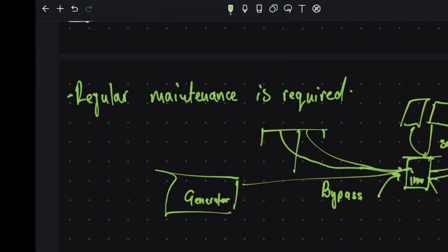It has been used all night. The batteries are finished, so they need to charge. It needs electricity from somewhere. It goes to bypass mode and sees that the normal electricity is not working. Then it will automatically switch to generator.